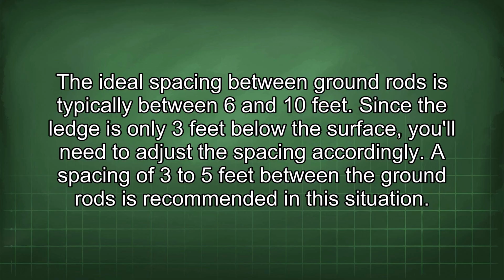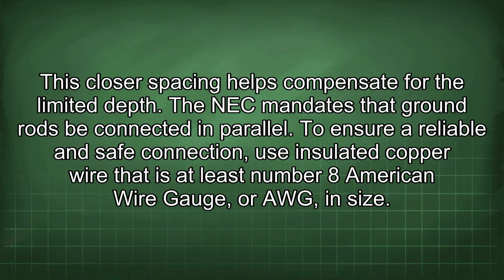The ideal spacing between ground rods is typically between 6 and 10 feet. Since the ledge is only 3 feet below the surface, you'll need to adjust the spacing accordingly. A spacing of 3 to 5 feet between the ground rods is recommended in this situation. This closer spacing helps compensate for the limited depth.